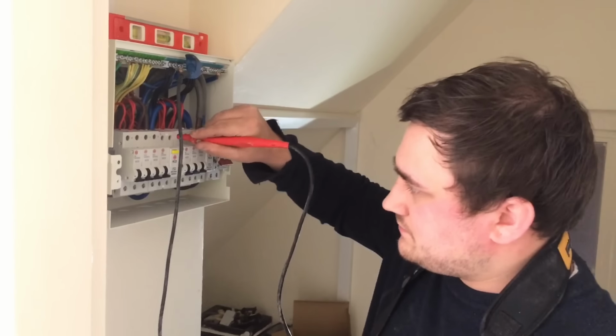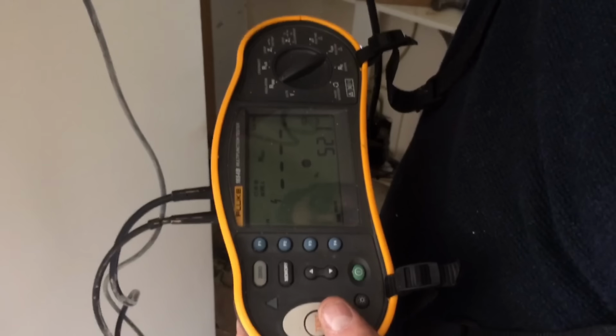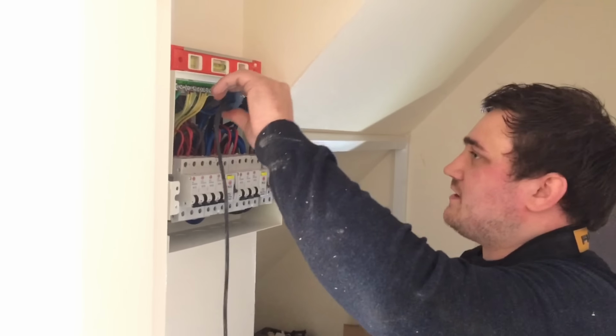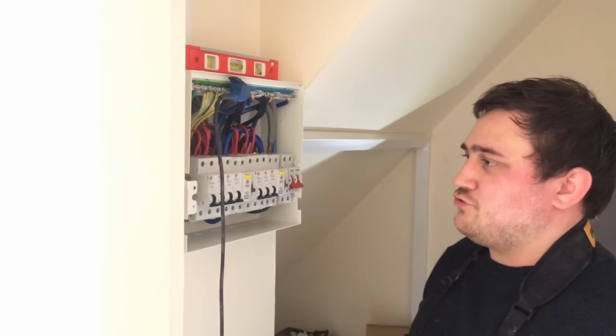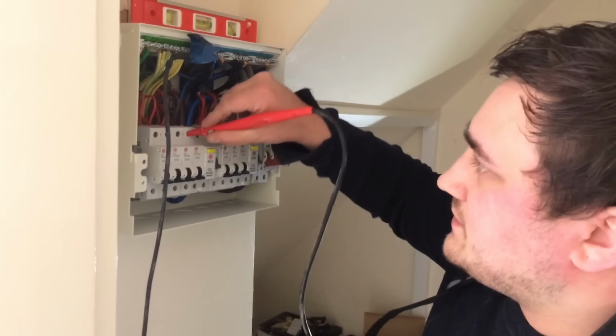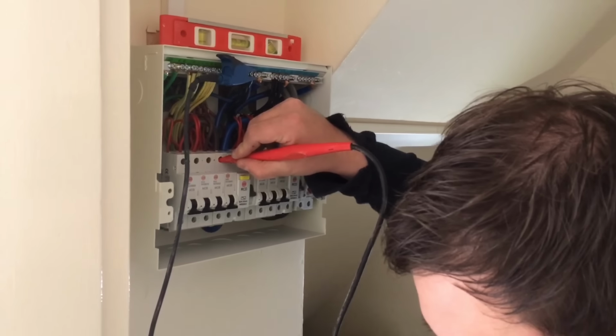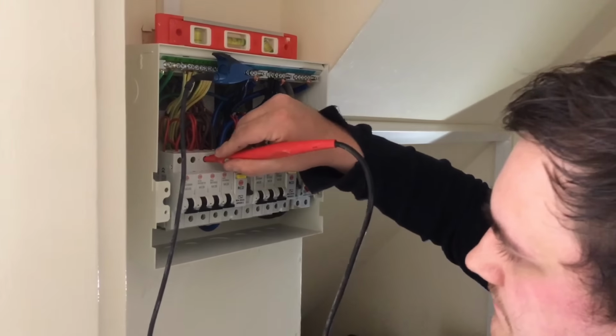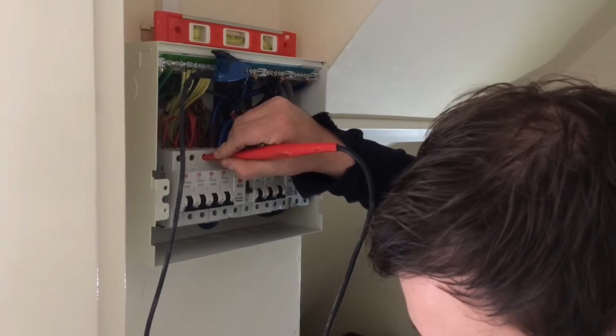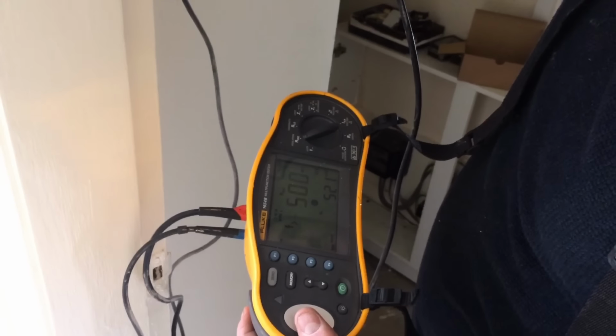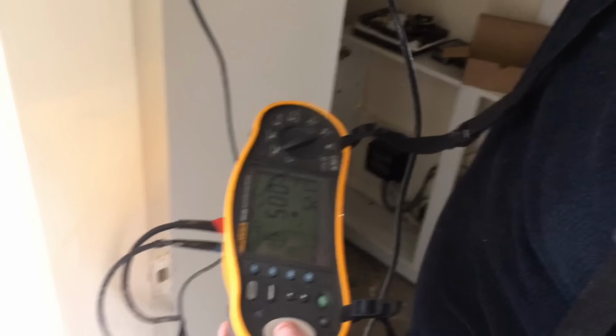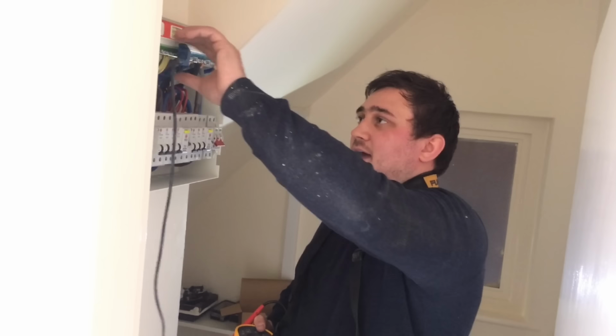500 megaohms and 500 megaohms. I'm now going to move on to the other RCD, which is a different neutral bar. Same principle: 500 megaohms, 500 megaohms, 500 megaohms and 500 megaohms. That is the line and neutral insulation resistance test.